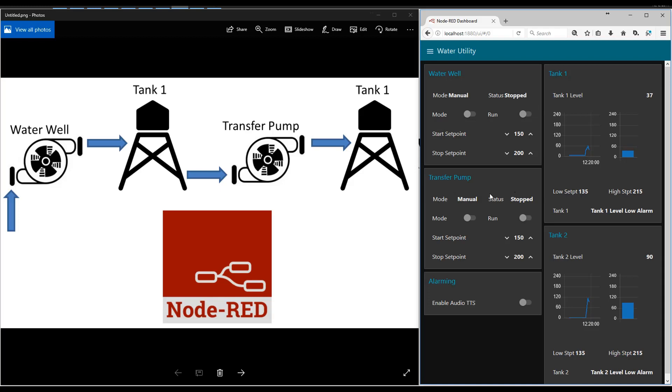And we also have an automatic mode. So if I put this guy in automatic, it will automatically start if the level is below 150 and stop if it gets above 200.